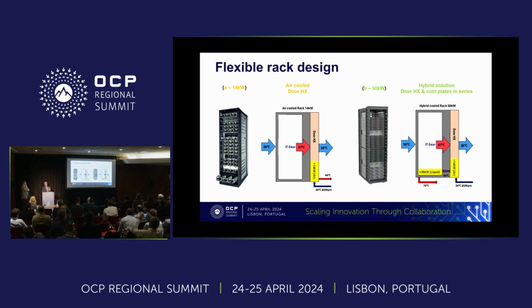The flow rate per rack is 20 liters per minute. When we shift to liquid cooling, we have the same flow rate, but in serial connection. We connect liquid cooling and can achieve 70 degrees with certain on-chip cooling technology, and 36 kilowatt now is cooled by direct-to-chip. So overall we have 50 kilowatt per rack, but the same flow rate, same facility, tubing design, same pumps, etc.